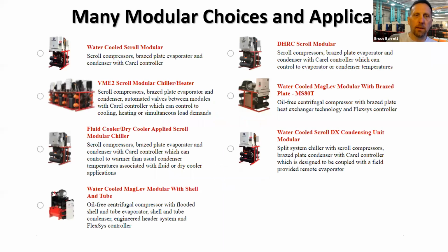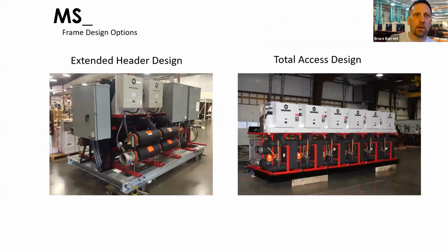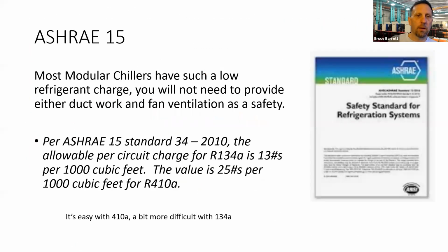We did have one question that came in through another way here. Do the MSF flooded modules still meet the low refrigerant volume to avoid a refrigerant ventilation system? Good question. First calculation would be to calculate your equipment room cubic feet. For 134A, that's about, I have to go back, I'll go back to that slide. There we go. Nope, I lost it.